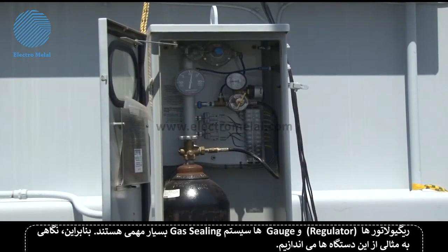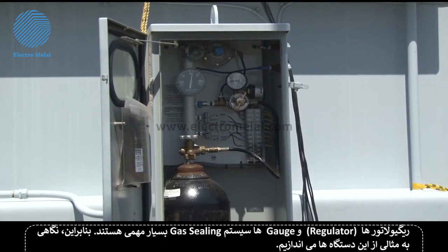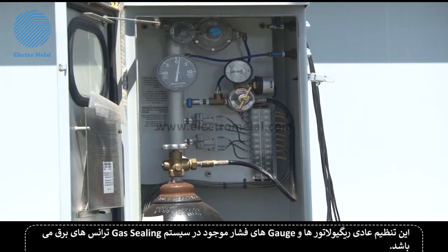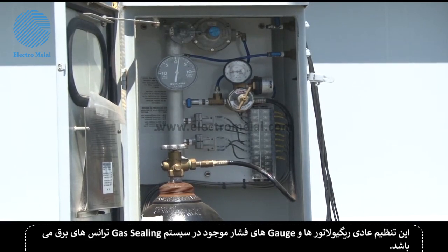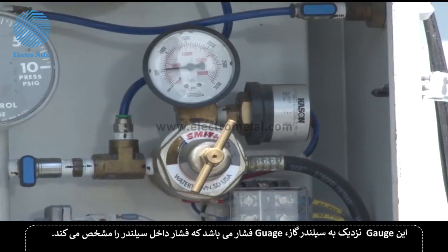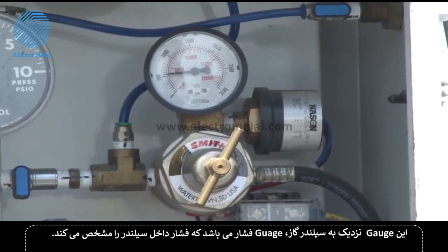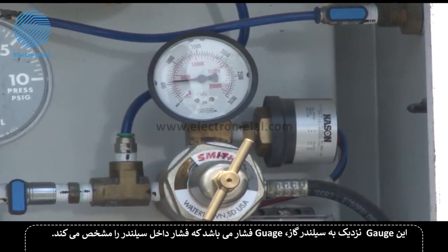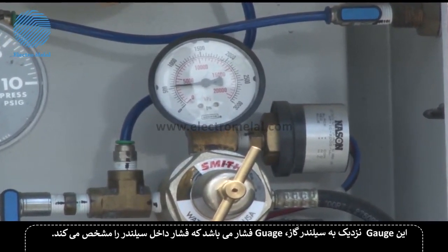The regulators and gauges are an integral part of a transformer gas sealing system, so it's worth our while to look at an example of these devices. This is a typical arrangement of pressure regulators and gauges found with power transformer gas sealing systems. This gauge, closest to the gas cylinder, is a pressure gauge that indicates the pressure inside the cylinder.